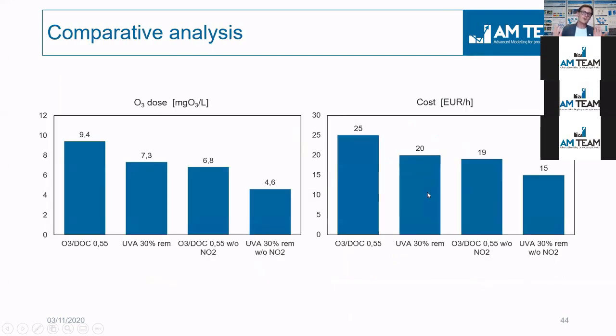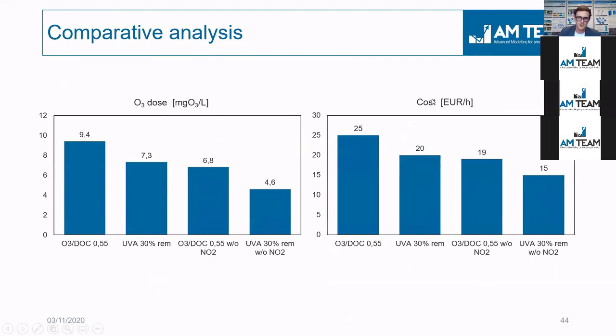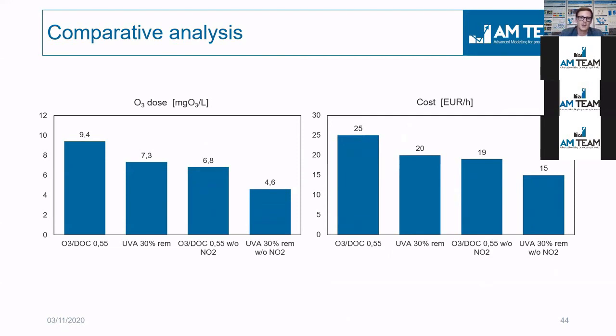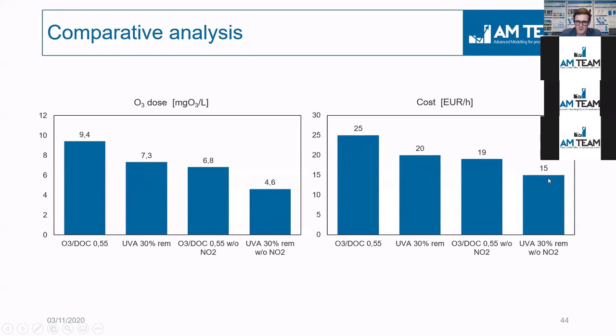Again, you can do a very easy comparative analysis in terms of ozone dose needed average, and also the cost per hour, the cost per hour in this plant. But, of course, very much of this work and a very nice study has been done by the CW Pharma people. It has all been published, and this is available. So we didn't, in this case, we didn't come up with the equations to measure the cost. We started from their equations. But you can see the impact on nitrites. It's easily 5 euros an hour less. Imagine you wouldn't have no nitrites.